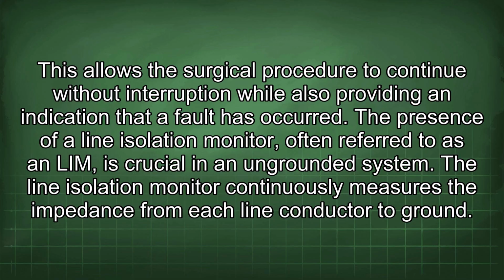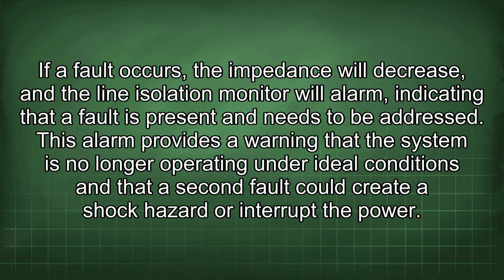The presence of a line isolation monitor, often referred to as an LIM, is crucial in an ungrounded system. The line isolation monitor continuously measures the impedance from each line conductor to ground. If a fault occurs, the impedance will decrease and the line isolation monitor will alarm, indicating that a fault is present and needs to be addressed. This alarm provides a warning that the system is no longer operating under ideal conditions and that a second fault could create a shock hazard or interrupt the power.